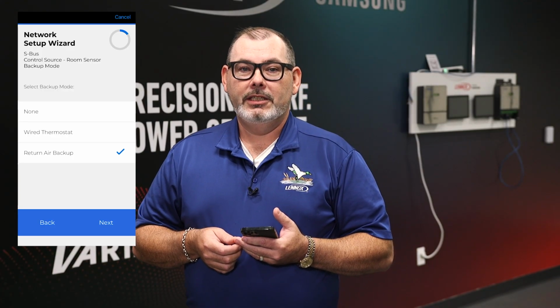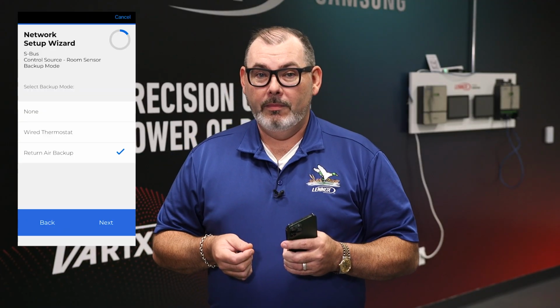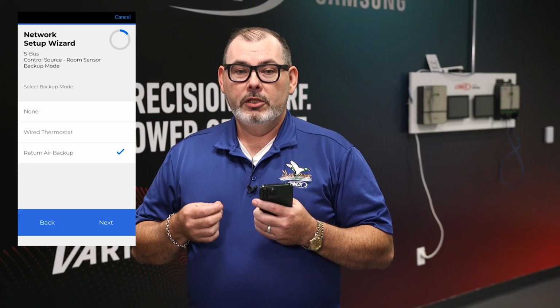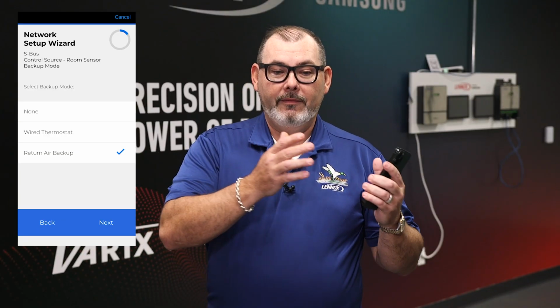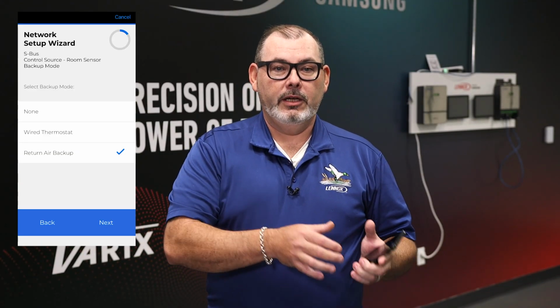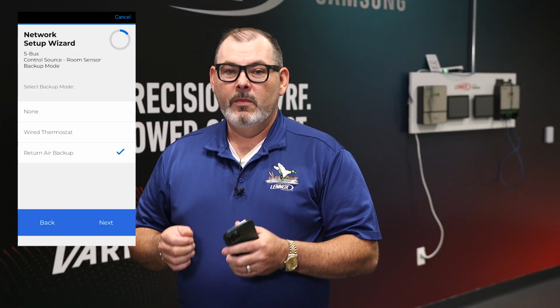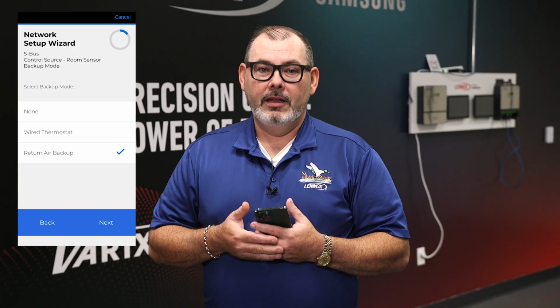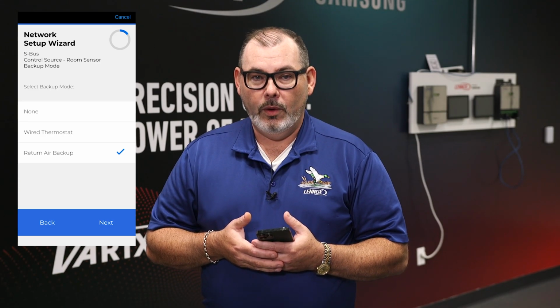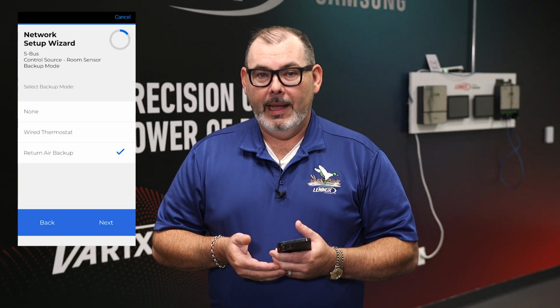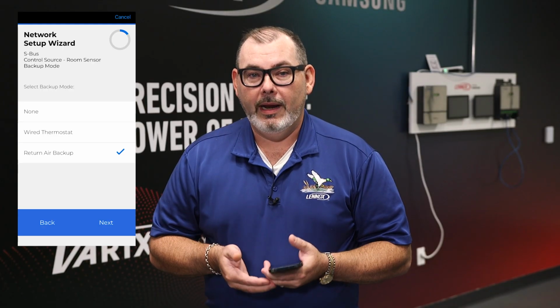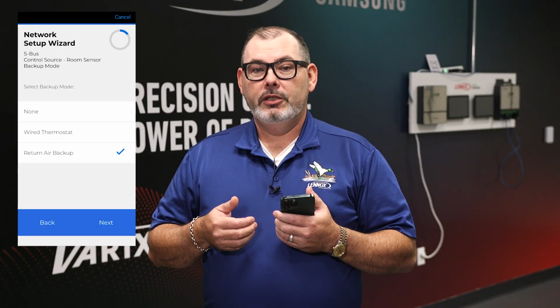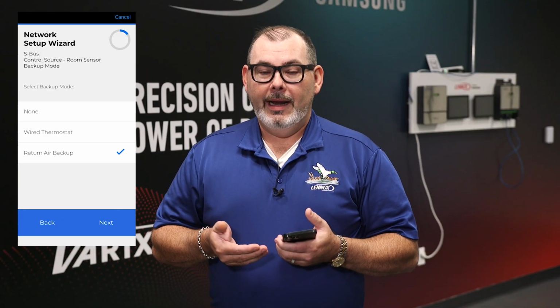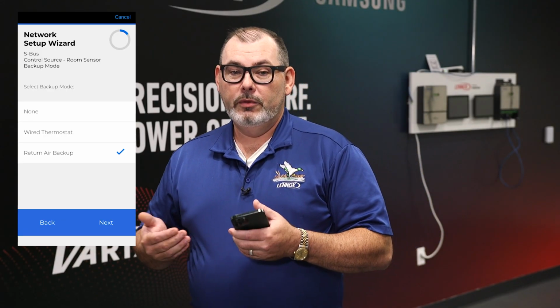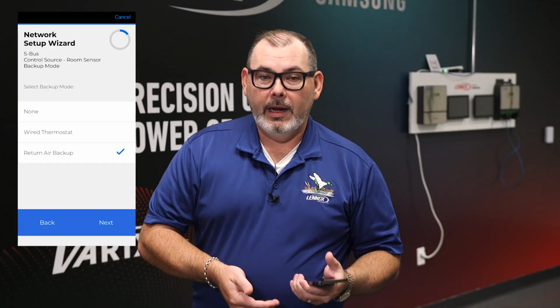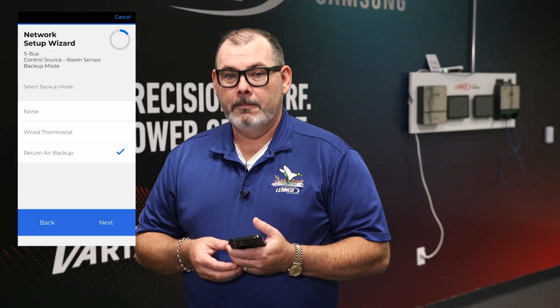At this point, you've reached the time where you need to select your backup mode. Backup modes will get you to a fail-safe situation where I've lost my controls, and after I've lost my controls, the unit is going to run in backup mode. If you're in backup mode, it's very important to select the temperatures and what you will be setting it for. Do you want to set it for a wired thermostat backup? Do you want to set it for a return air backup? Do you want to not have a backup? Return air backup is the most popular because you don't have to run a thermostat wire to run a thermostat backup and mount it in the space.